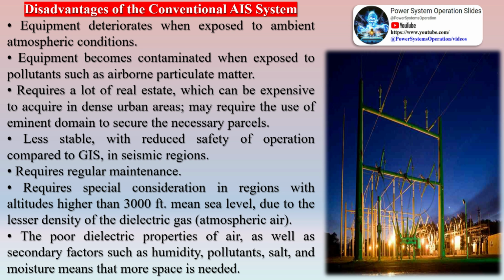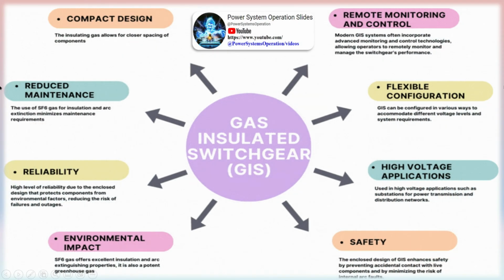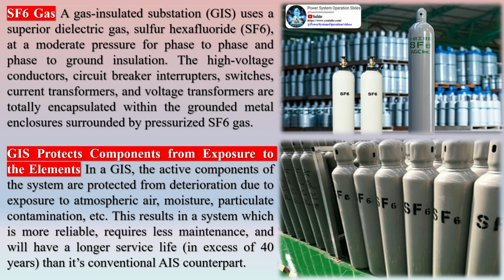Requires regular maintenance. Requires special consideration in regions with altitudes higher than 3,000 feet mean sea level, due to the lesser density of the dielectric gas, atmospheric air. The poor dielectric properties of air, as well as secondary factors such as humidity, pollutants, salt, and moisture, mean that more space is needed. A GIS substation uses a superior dielectric gas, sulfur hexafluoride, SF6, at a moderate pressure for phase-to-phase and phase-to-ground insulation.